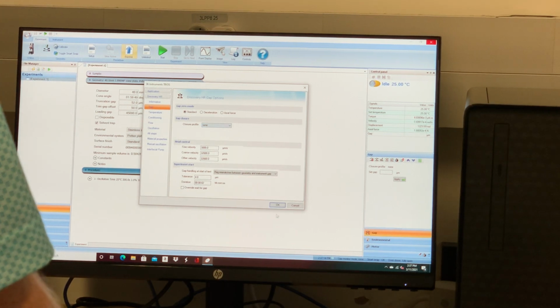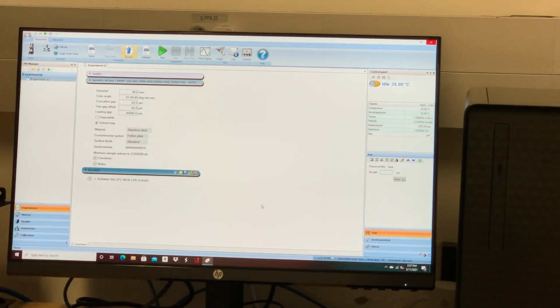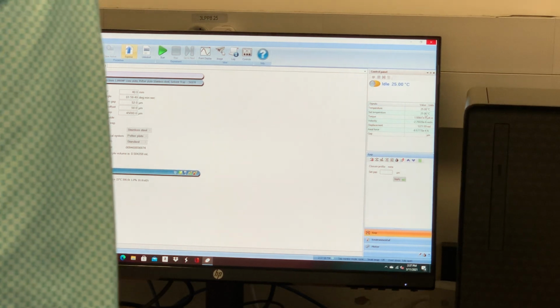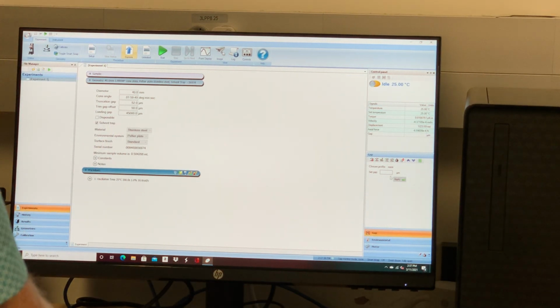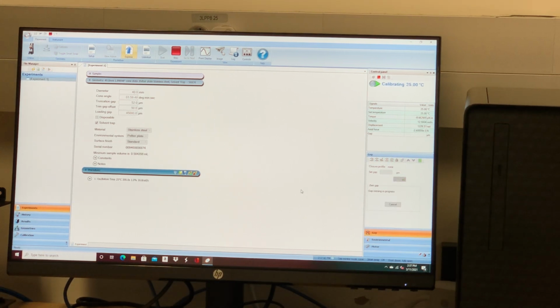The closure rate, once it gets pretty close to the bottom plate, it's going to slow down. But you may have samples where you don't want it to squeeze the sample out, so you may want to go really slow. So that would be a function you could change. Okay, so we're at 25C. We can zero it. We go to zero gap, and it's going to turn the geometry.